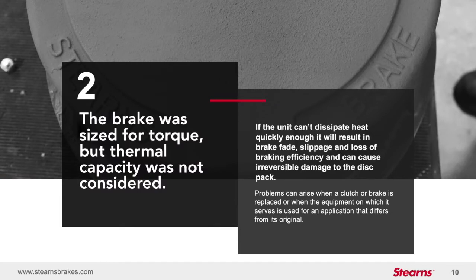After determining the general type of brake for a particular system, sizing for optimal performance and long life are next on the agenda. Mistake number 2 is the brake was sized for torque, but thermal capacity was not considered. The brake should be set up to handle whatever load is applied to it. If you don't factor in thermal capacity, most likely you will have longer stop times and it will cause the brake to heat up a lot faster and therefore dramatically shorten the life of your brake.